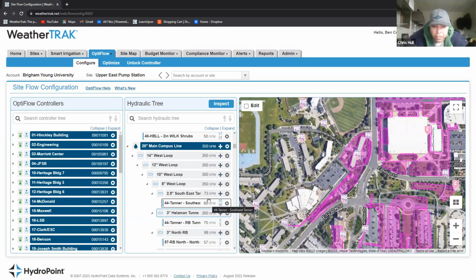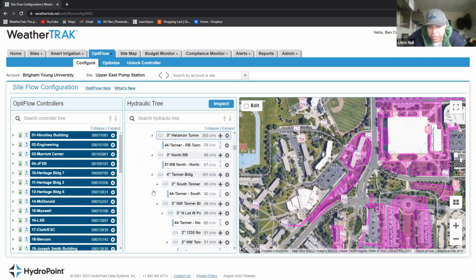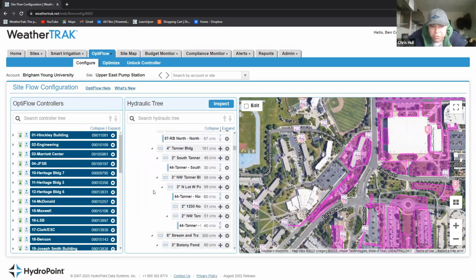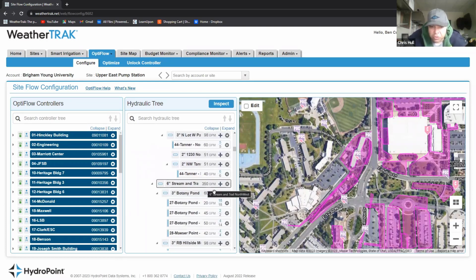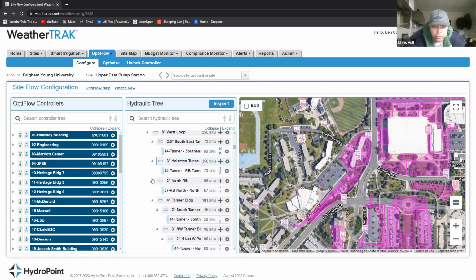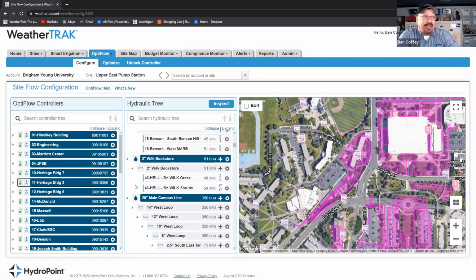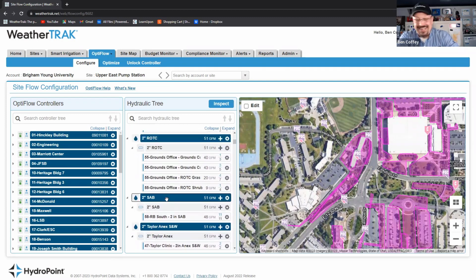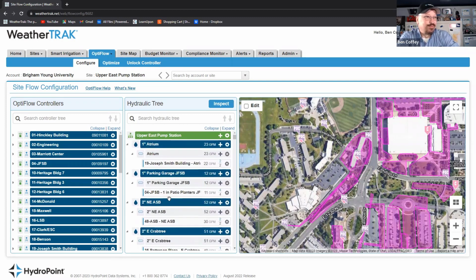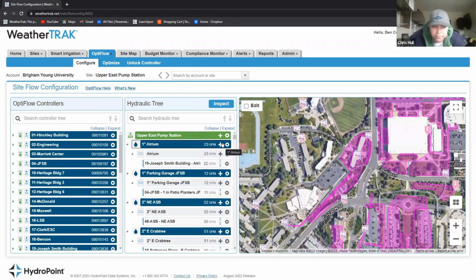Yeah, and sometimes you won't have a lot of good as-builts. I mean, some people have good as-builts, and we have a good system where we use AutoCAD, and we know what sizes are there. Sometimes we have to go out and verify that. And sometimes when we're doing renovations, we run into situations where we find out this isn't a 2-inch line, it's a 3-inch, so then we can put those numbers in there and adjust it accordingly. So it's flexible enough to put it in once and then change it as you verify the reality out there, right? That's right, that's awesome.